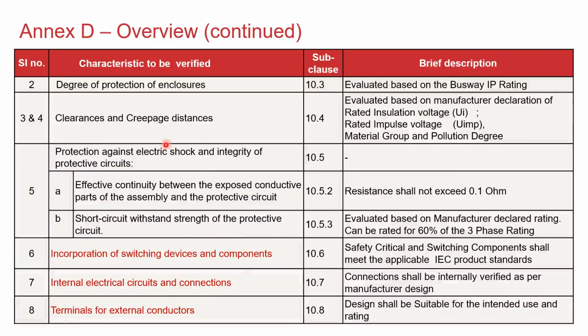Then we will have a quick overview of the other tests. Then you have the degree of protection of enclosures. This is a very important subject. The reason being, the IP is determining your ability to use and also the ability to provide protection against ingress of dust or water. So that is determined based on what the manufacturer declares.